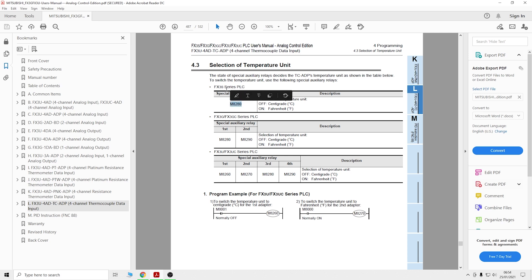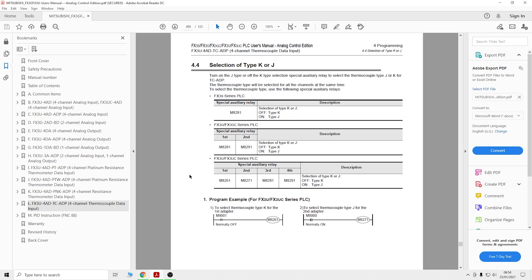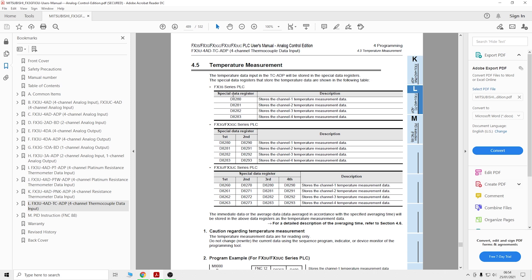For the selection of temperature unit, M8280 - once you turn this bit on it will read centigrade or Fahrenheit. Remember the digital value representation is different for Fahrenheit and centigrade. For our FX3S card, the first card uses this bit. For selecting J type you need to make sure M8281 is on for the FX3S series first card. You can see for the second card it would be M8291 for the 3G, and similarly for the 3U series PLC. Temperature measurement is stored in D8280 for channel one, and then D8281, D8282, D8283 for the respective channels.